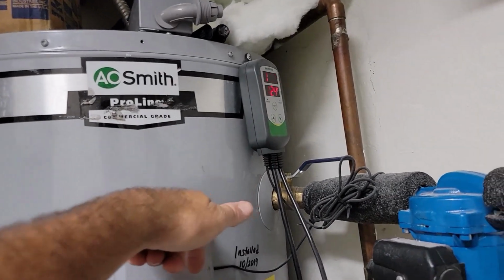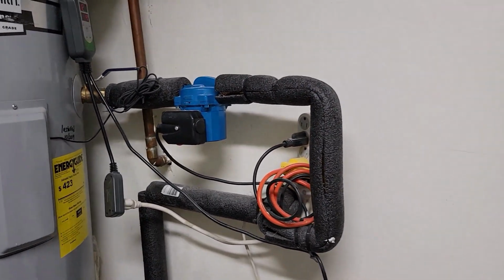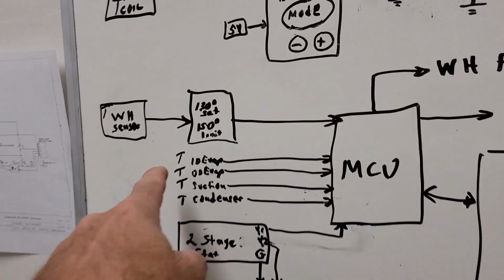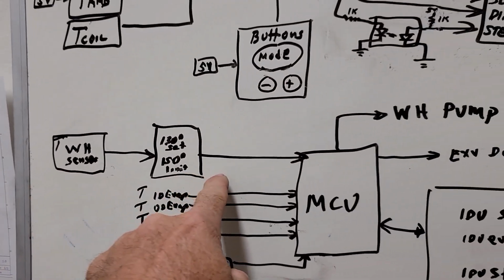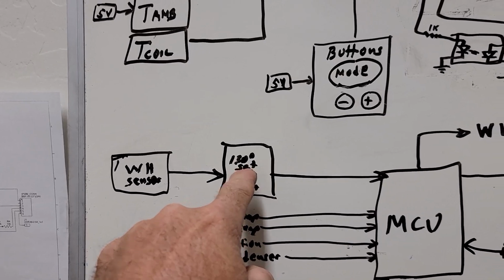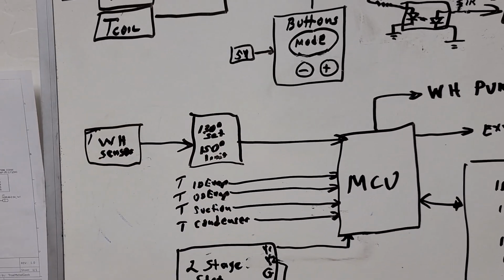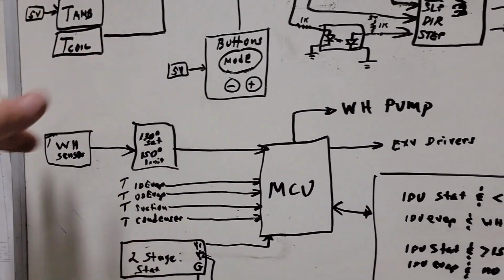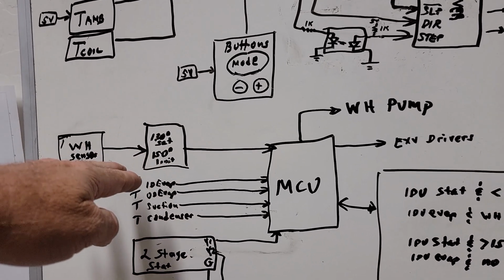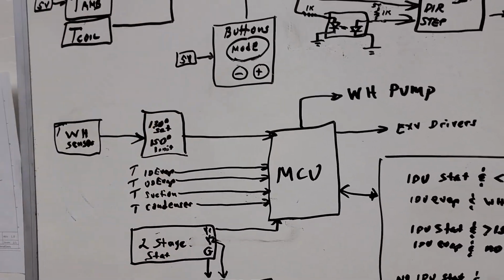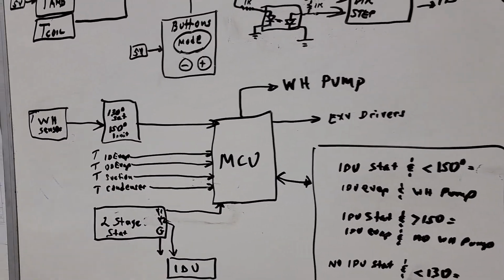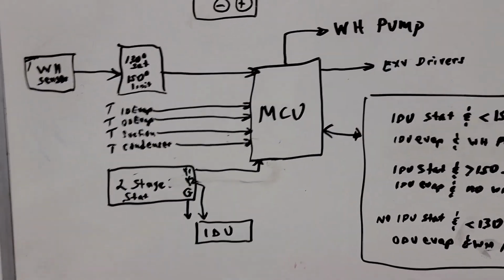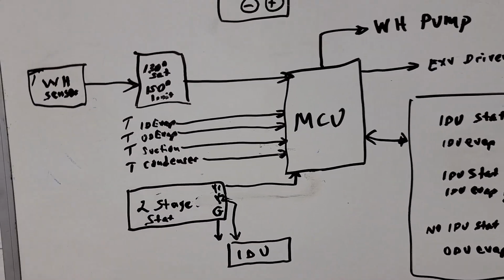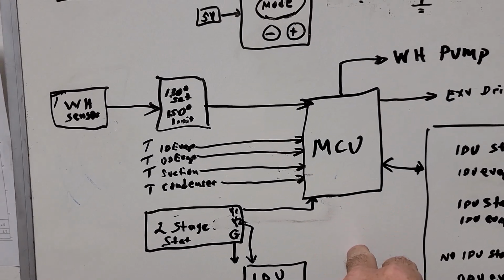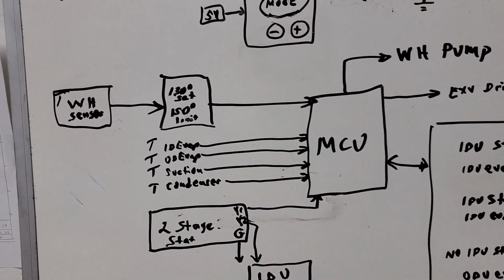I might just stick a thermistor in there for my own reading. It'll read the temps from the water heater sensor, with two modes: a 150 limit and an approximately 130 set point that it'll normally run at. Anytime it goes below that differential, it'll run the compressor. If it's too cold in here, or isn't calling, it'll just use the outdoor evaporator.